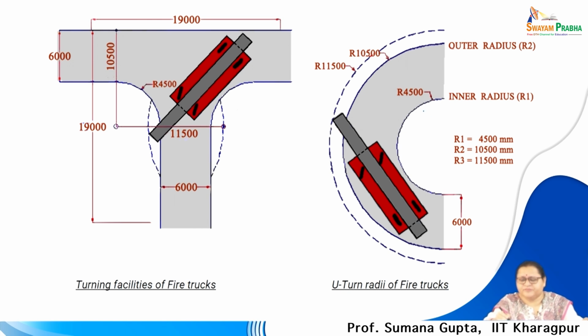So, the radius of curvature, the outer radius for a fire tender to move, is important, from very small buildings to complexes, places where there are multiple buildings, building complexes or residential towers. At all points it should follow these norms. Otherwise, the fire tender cannot reach the building they are targeting, and that too a high rise building. So, these dimensional requirements, when you are working with the site plan, are to be first chalked out, and these are to be considered on the road spaces, and no open space, that means mandatory open space, should be encroached by any parking.